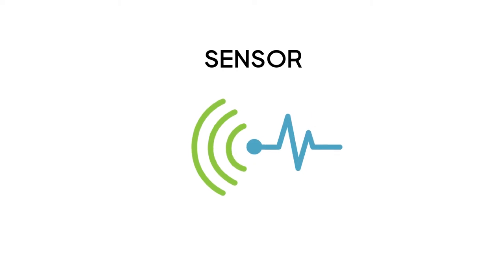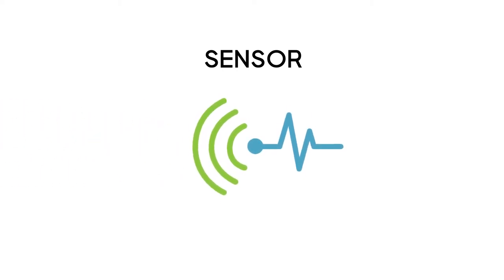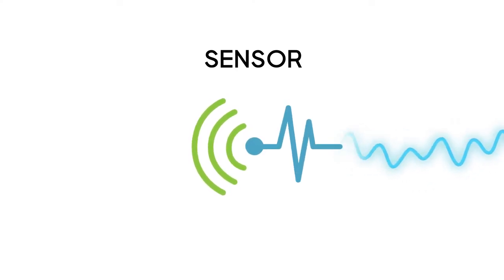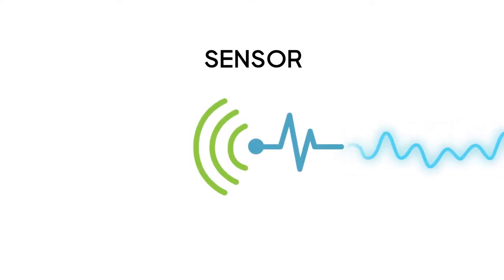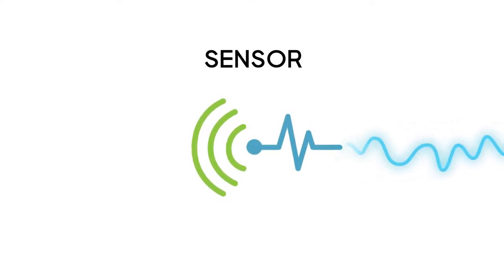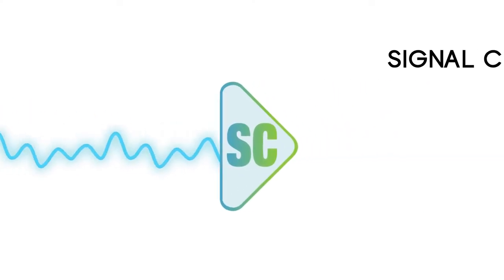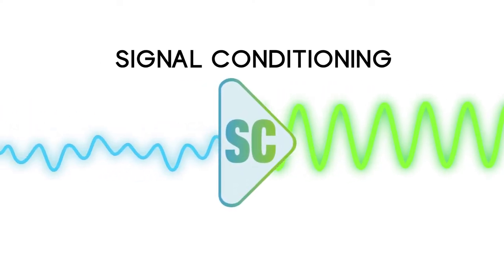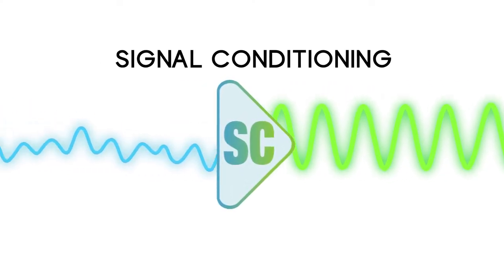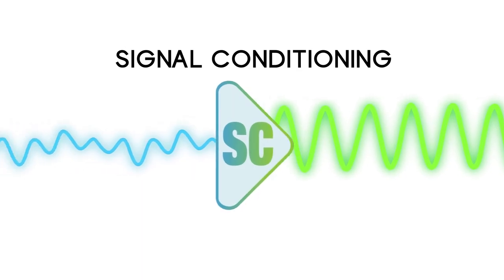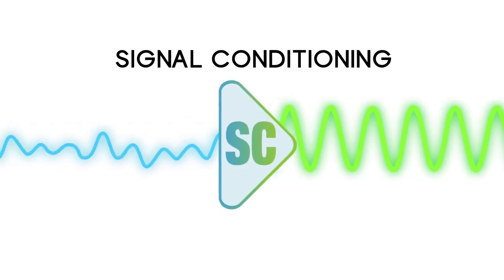First, a sensor measures a physical parameter such as temperature, humidity, pressure, or flow, and outputs a quantifiable electrical signal — depending on the type of sensor, either voltage, current, or resistance. Next comes signal conditioning. This is where the raw signal from the sensor is either amplified or attenuated depending on the line level requirements of the system.